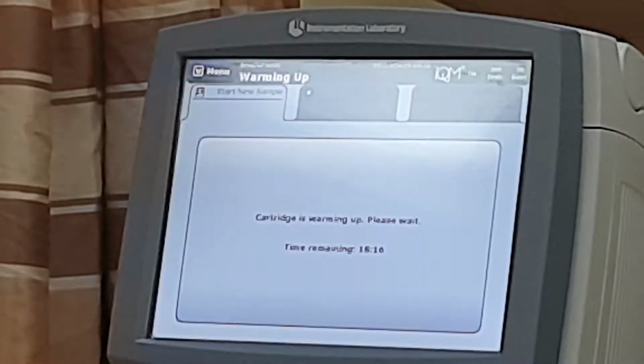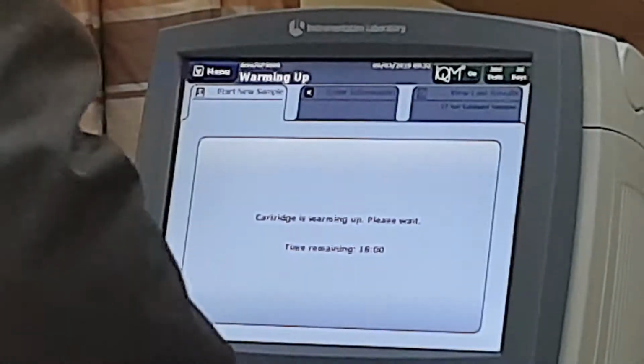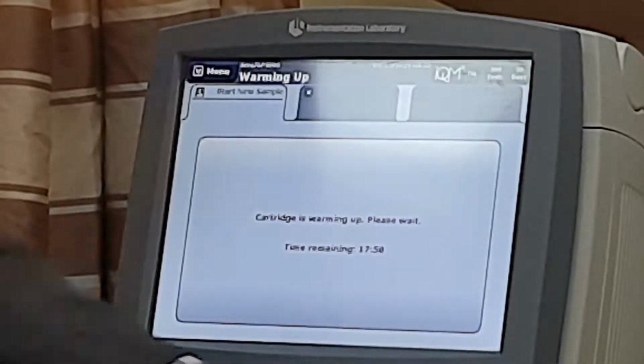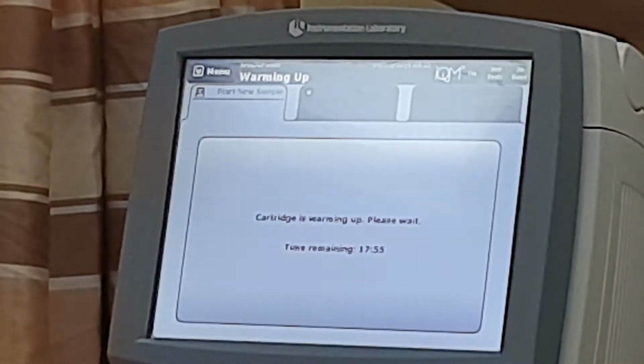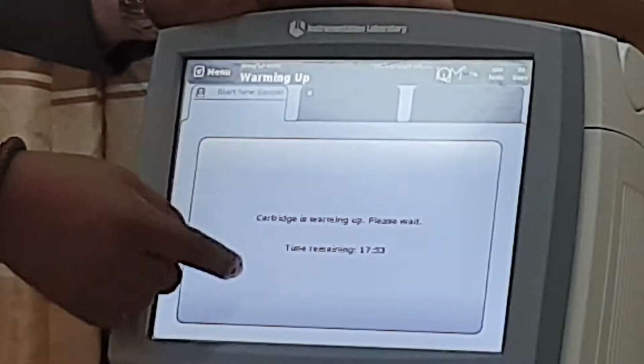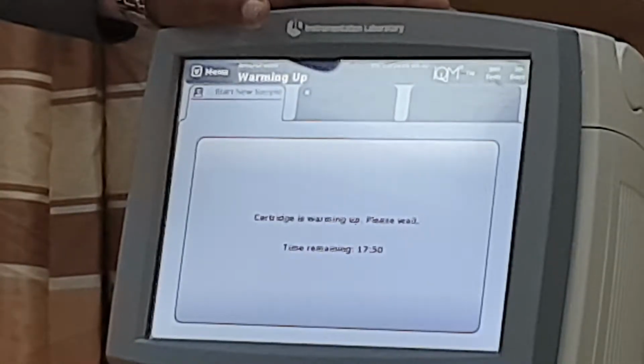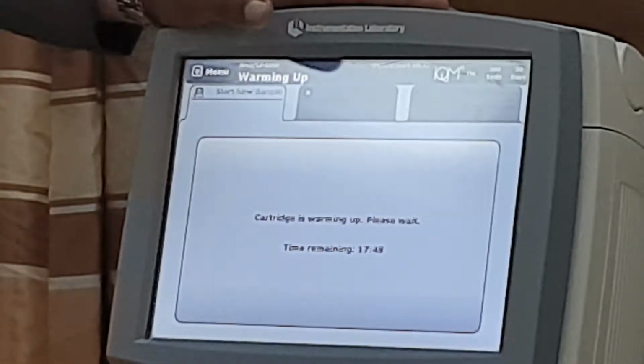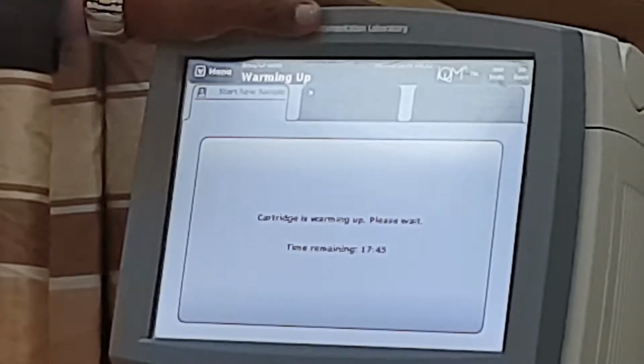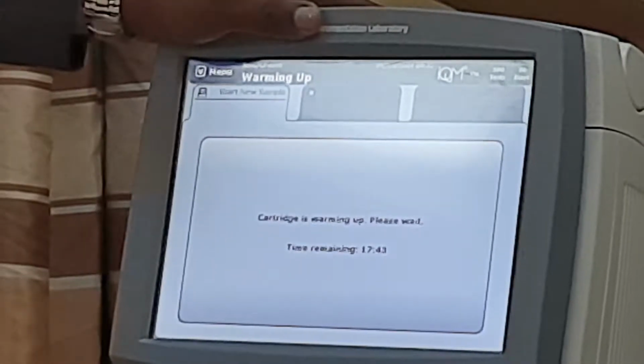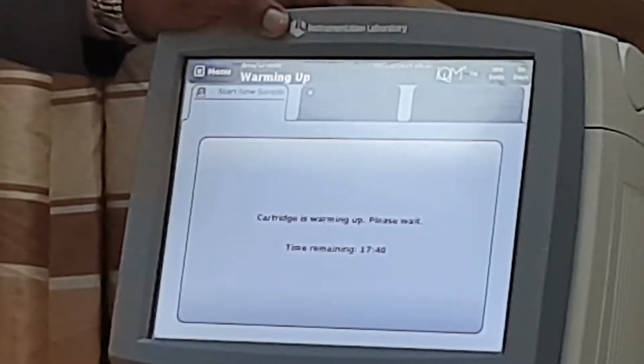After I insert the cartridge, it's better if I come 20 minutes before to show you how to insert it. It's very easy. It's a gray box. We just open the door, insert it inside, and close the door directly. After that, the machine, as you are seeing here, will take 40 minutes for warming. What I mean by warming is that the machine runs to prepare the solution and everything inside, to check whether the cartridge is working well or not.